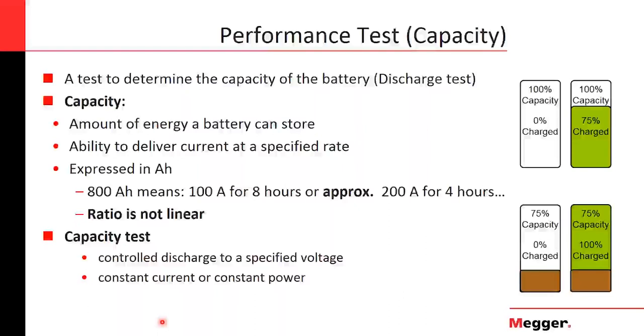And one thing that you might think is that the battery ratio is linear: if it can give me 800 amp hours in 8 hours, or 100 amps constantly for 8 hours, it might be able to give me 200 amps in 4 hours. But this ratio is not linear. We're going to see a table which shows that.